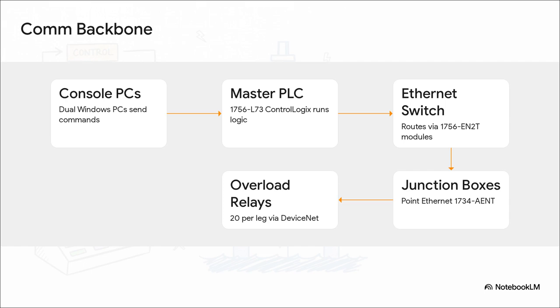Your commands travel over an Allen Bradley Industrial Ethernet/IP protocol. The whole thing starts right at your dual Windows console PCs in the control room, runs through a master Allen Bradley ControlLogix 1756L73 PLC, which is essentially the absolute processing brain of the entire setup, and pushes through an Ethernet switch. From there, the data packets hit the point Ethernet modules down in the junction boxes. And finally, they reach the 20 E3 overload relays on each leg via a DeviceNet scanner.